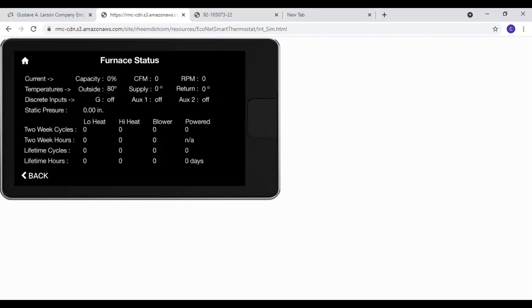And then that will tell you if this is above 1, it's high. If it says it's unknown, it means it's so high it can't calculate it. So ideally, you want your static pressure below 1. So anything below 0.99 and down is acceptable. 0.99 is still high, mind you, but it's below the max. So here's your static pressure.